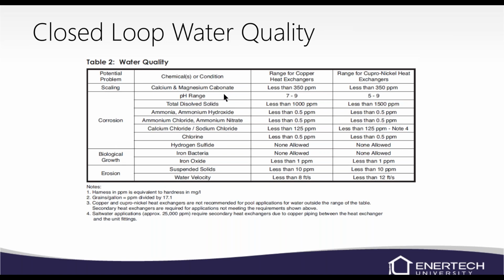But normally when we bring it back, or those test kits, we test for the pH, ammonia, chlorides, iron, copper, ammonia. I think I might have already said that one. And we can also check for inhibitors. If we have a water sample from the home and a water sample from the loop field, we can compare the two and see if you've got inhibitors in your antifreeze. Inhibitors are used for rust and saving the different metals in the system. Most antifreezes have inhibitors in there. I would not recommend using RV antifreeze because it's not. So don't use RV antifreeze from the AutoZone or whatever.